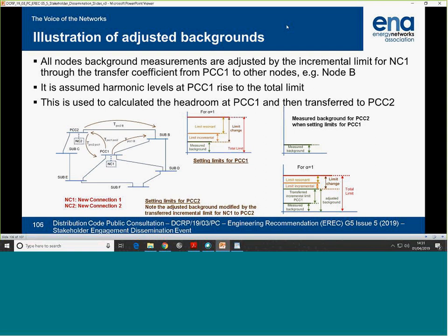But now I have to estimate the impact of this guy on here. I know new connection 1 has an allowance to cause a range of harmonic level at this point according to the incremental limit I've given them. If they are going to do that, I know they must not exceed that. That's the limit. So this is what I'm going to do. I assume we're going to use that.